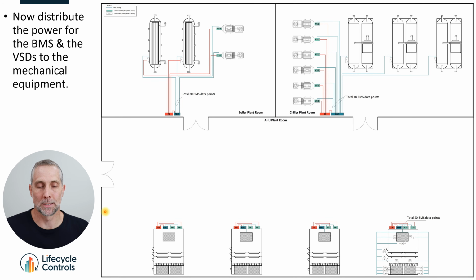So rather than having a centralized, very large 5-meter mechanical control panel, which I'll just pause for a second. My experience, a long time ago when I used to do this, is that it would take about 3 months from just starting to think about the mechanical control panel, design the control panel, get it approved, get it built and sent to site on a concrete plinth and install. That's a 3-month process. Straight away here, we've cut that out because these are standard distribution boards. They're not mechanical boards. There's no hand-off auto switches on there. It's an off-the-shelf distribution board with some 3-phase circuit breakers in there. You could buy them tomorrow and in 2 days' time, screw them onto the walls. So that's really quick to do. We're not wasting all this valuable, precious time designing this mechanical control panel, this centralized panel.